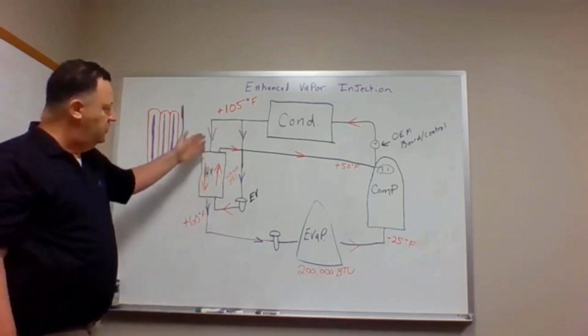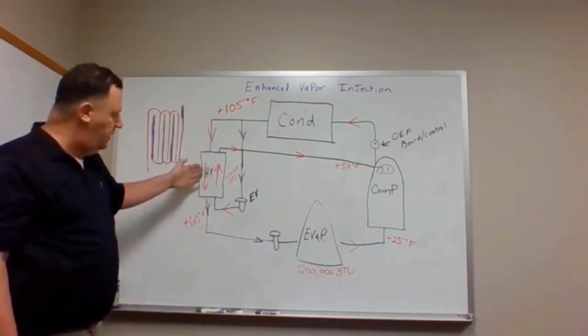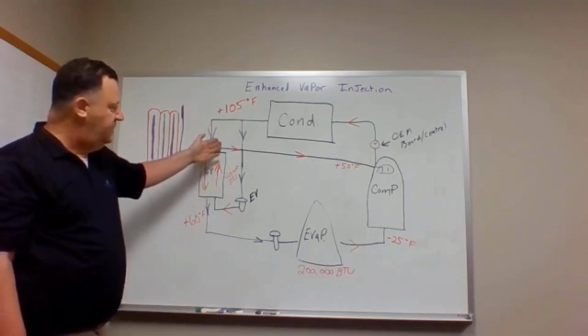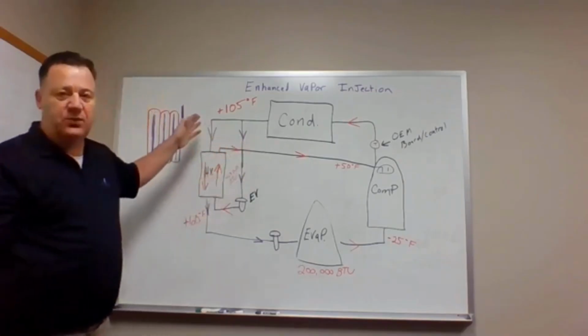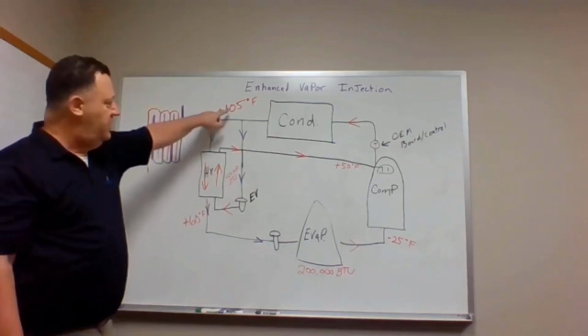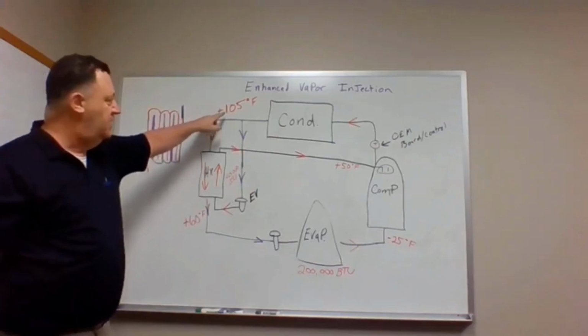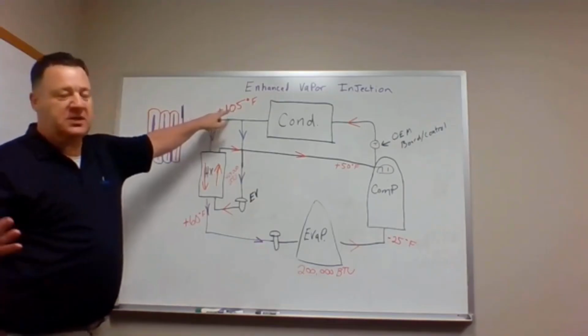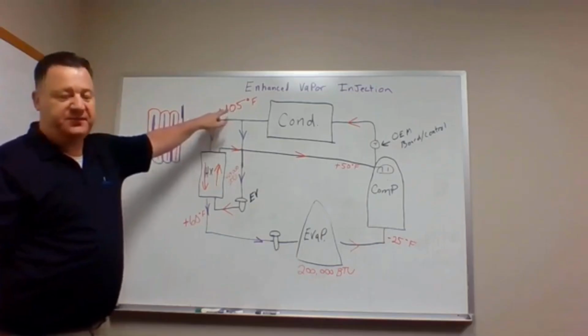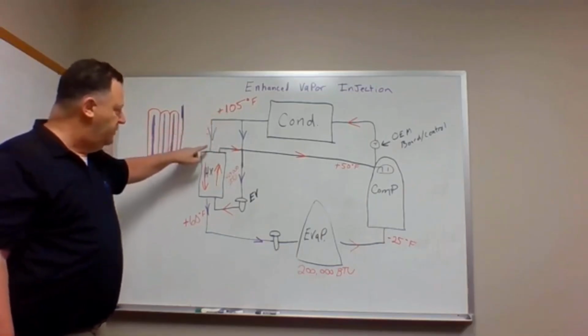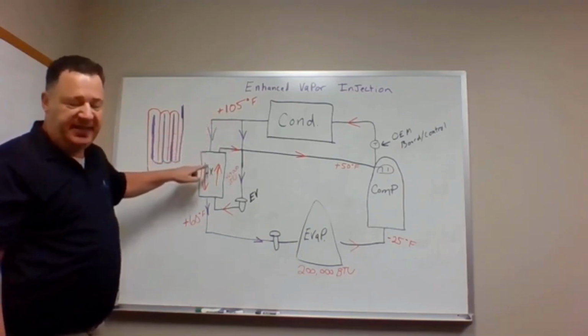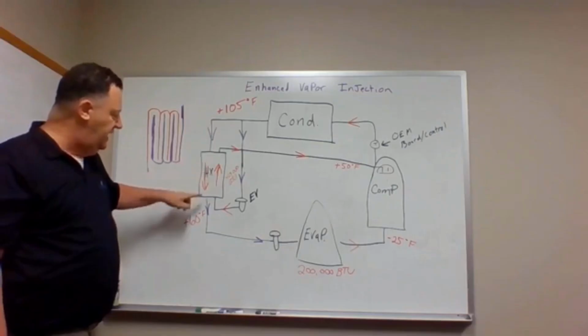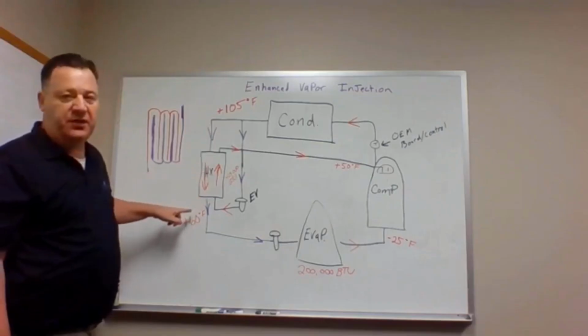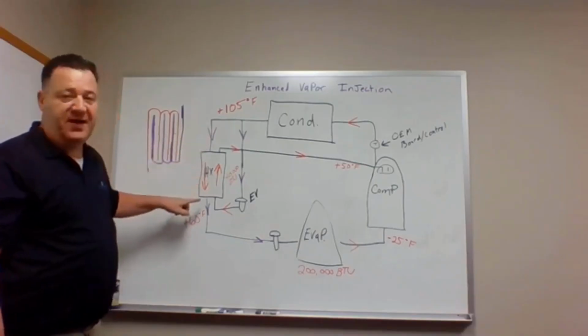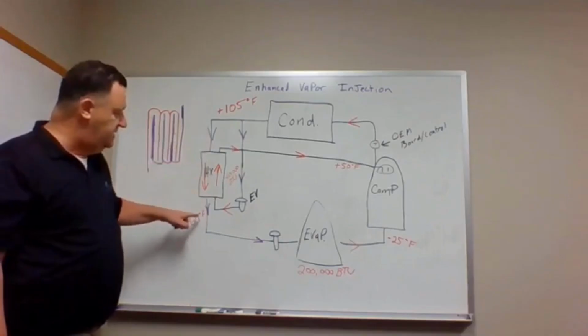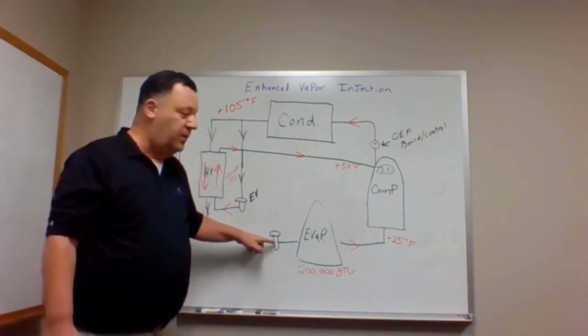And what they're doing is we're removing heat from the subcooled liquid to the vapor and picking it up and taking it with us. I'm going to stay with the liquid side for just a second. Notice, hypothetically, I just threw some numbers up here. We've got subcooled liquid at approximately plus 105, okay? As we come through the braze plate heat exchanger, pardon me, we remove that heat. I'm going to say we're going to move around 45 degrees.